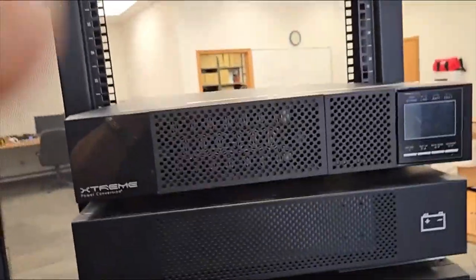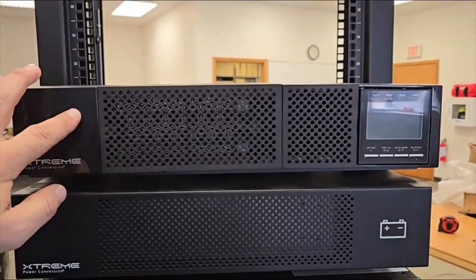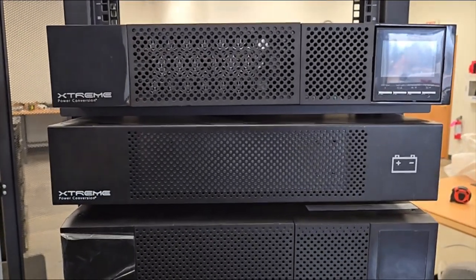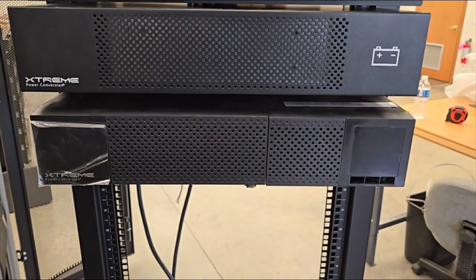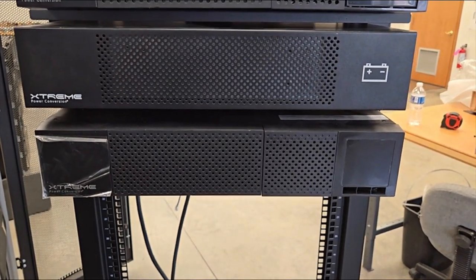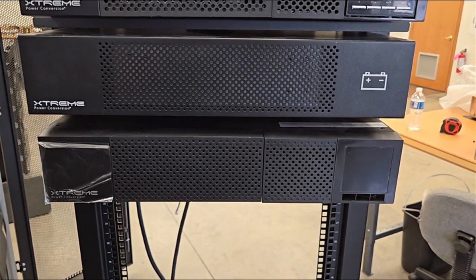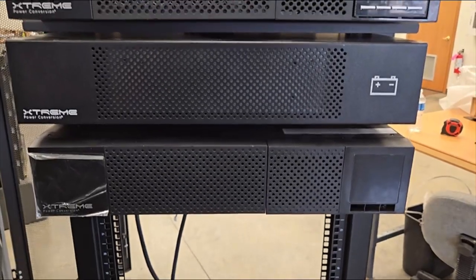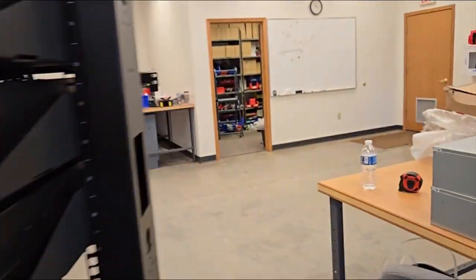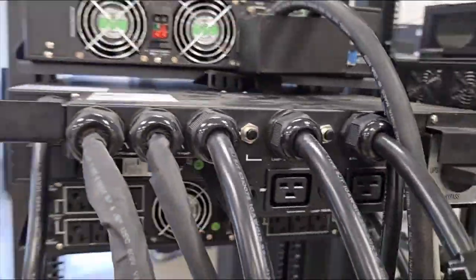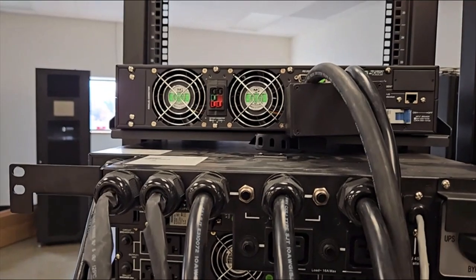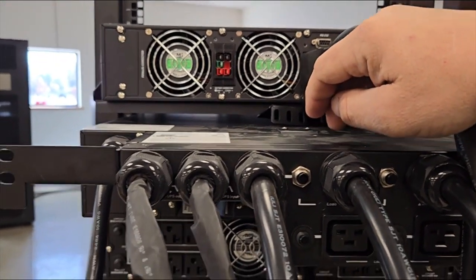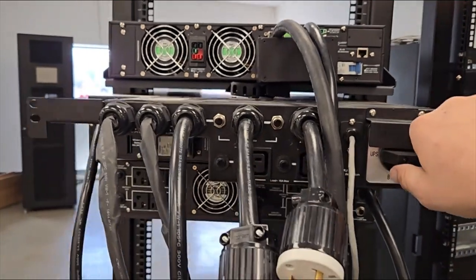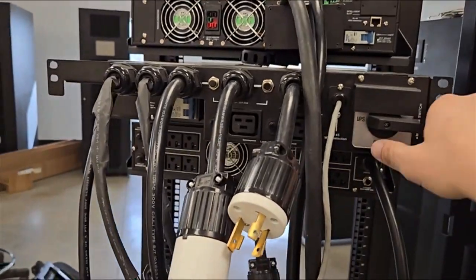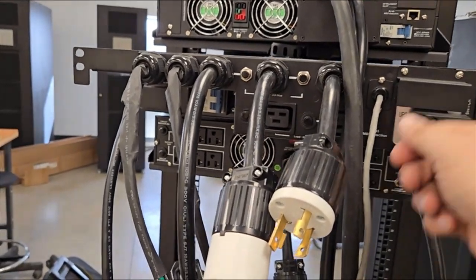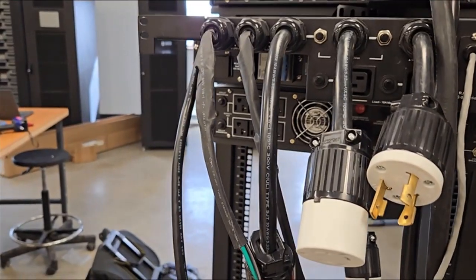I've got the UPS portion installed in the top shelf, the battery in the middle shelf, and the transformer module that steps the voltage down from either 208 or 240 to 120. I'll show you how those get connected on the back. Moving around to the back of the unit, we also have our P91A XBDM. This gives the user the opportunity to remove this plate and rotate this switch to bypass the UPS and put utility power directly to the load.